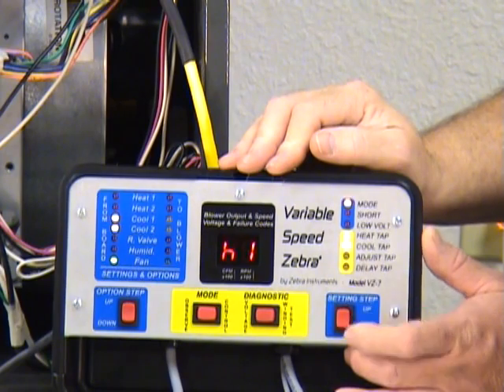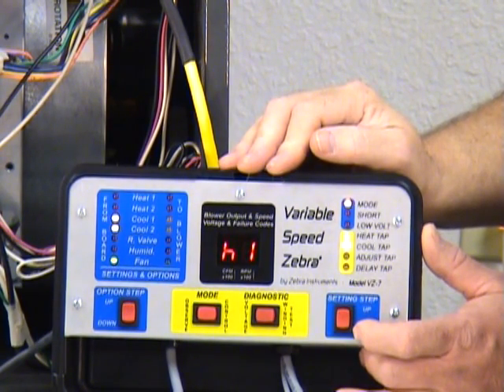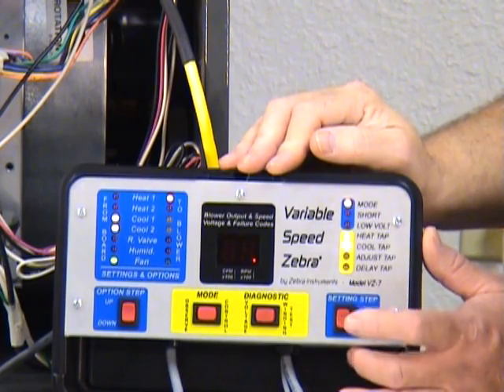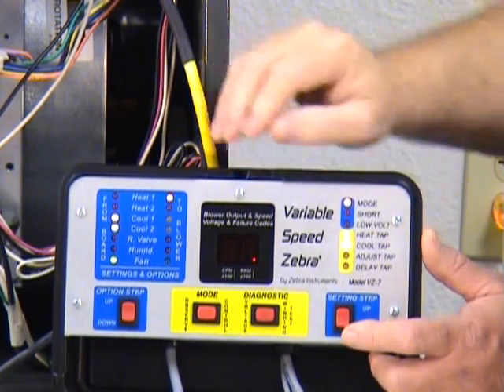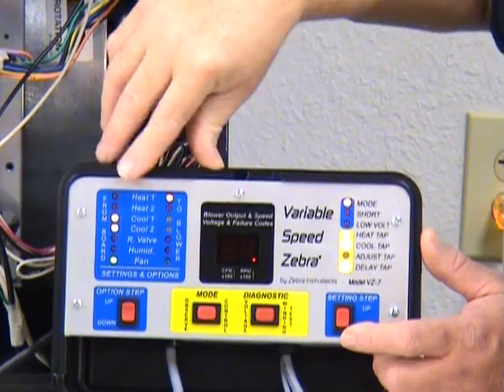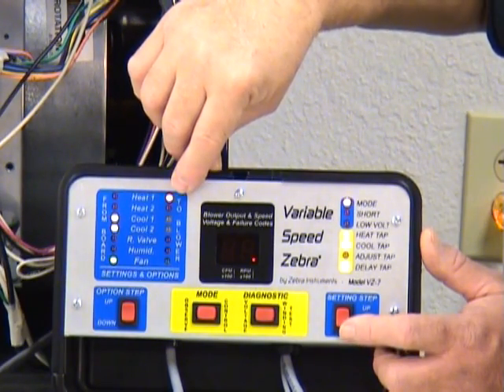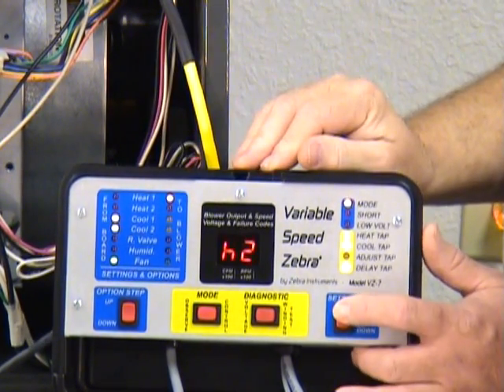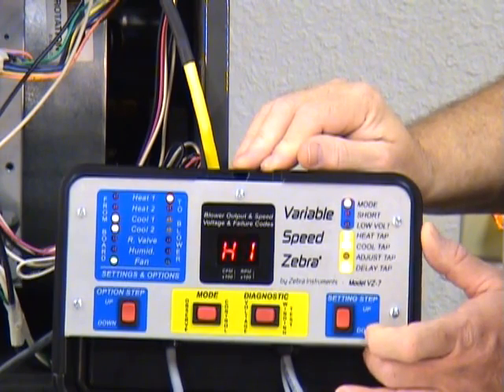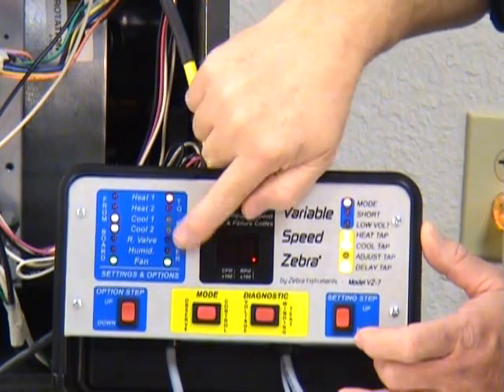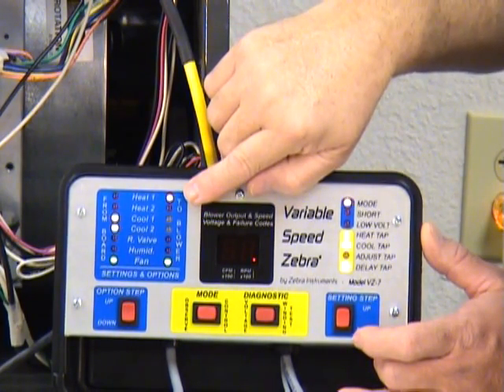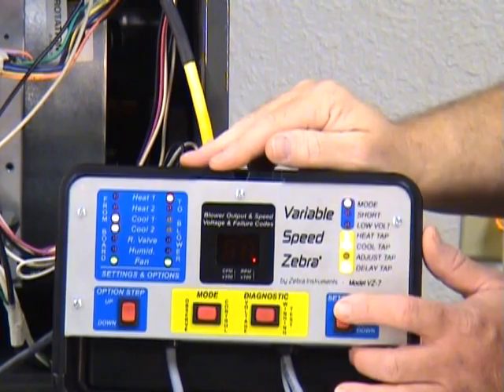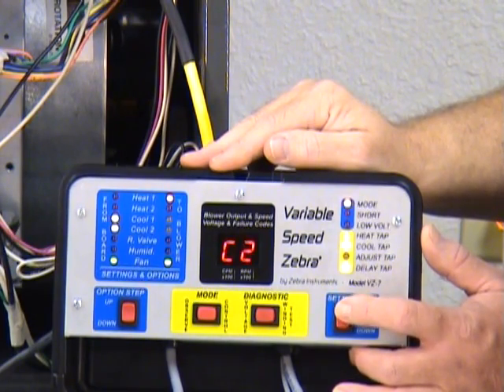But to demonstrate, we're going to go to a small H1, which is low speed heat. Five seconds after you quit pressing that switch, it will switch to that mode. So we see we only have the heat 1 mode light on right now. If we went, let's go up to a capital H1, five seconds later, it'll switch to that mode. The fan light will run simultaneously. Okay? So I'm explaining how to select which mode.